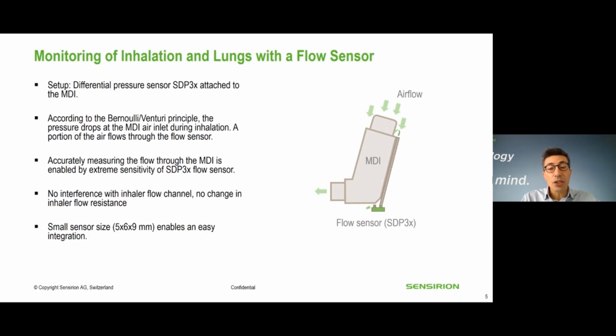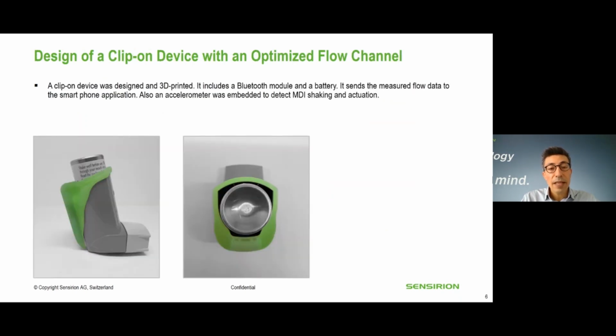We took advantage of the small size of the sensor of 5 by 6 by 9 mm in order to embed it in a small and detachable clip-on device to the MDI. The clip-on device was designed and 3D printed. The design of the PCB included, in addition to the flow sensor, a Bluetooth and microprocessor module, as well as a cell battery. We completed the electronic design with an accelerometer in order to detect the MDI shaking.